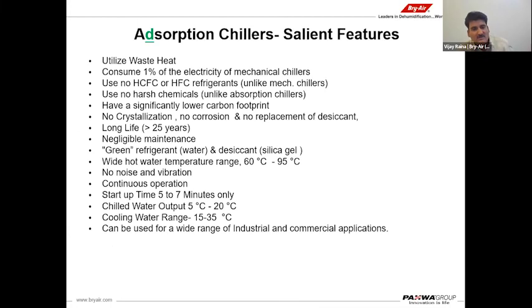With the adsorption chiller, everybody knows that we don't use HFC refrigerants, and our chiller consumes only 1% of the electricity. If it is a 100 TR screw chiller, which normally consumes 70 kilowatts of power, our 100 TR adsorption chiller will consume only 0.6 kilowatt of power. The rest will be run by hot water. Yes, definitely we need pumping power for hot water, which we can evaluate as per the hot water energy available with the customers.